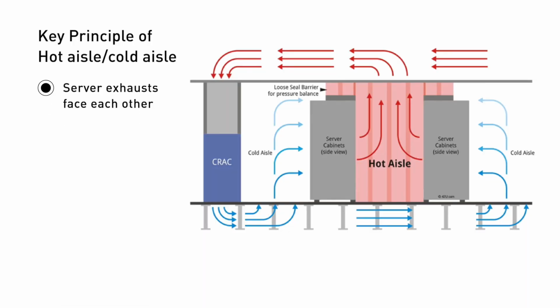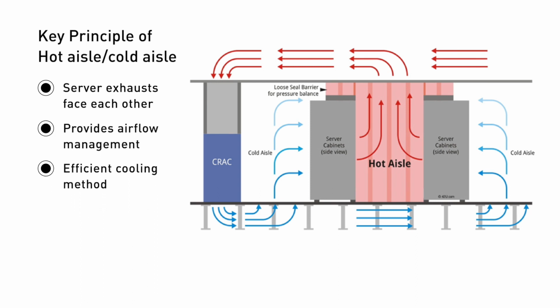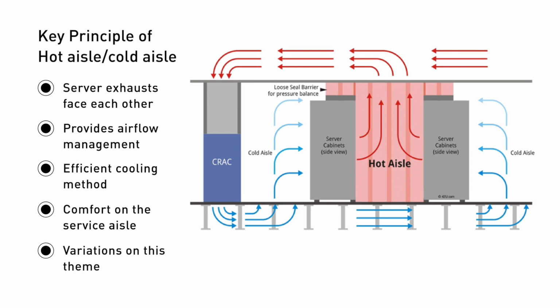So the cold side will generally be where the humans occupy the space, the engineers etc. And then the hot aisle, that air will be exhausted out and into the infrastructure to then be cooled around again. So the server exhausts face each other, providing airflow management and an efficient cooling method, while keeping the comfort on the service side for the engineers. Temperature ranges, you'll generally see around 50 degrees in the hot aisle and 25 degrees in the cold aisle - so both quite hot.